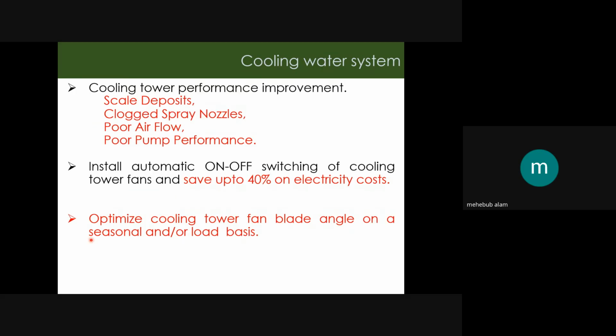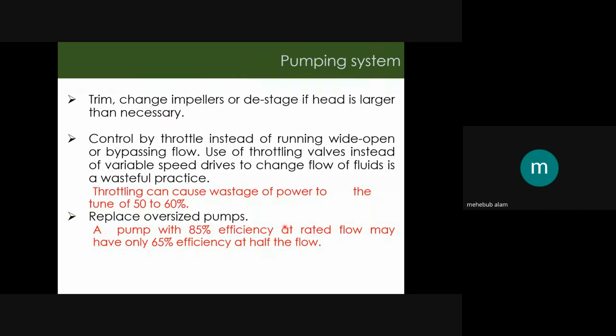In the cooling water system, we can improve the performance by proper monitoring of scale deposition, proper monitoring of airflow and pump performance, and the clogging of the spray nozzles. By installing automatic on-off switching of the cooling tower fan, we can save up to 30% on electricity cost. Optimize the cooling tower fan blade angle on a seasonal and load basis.